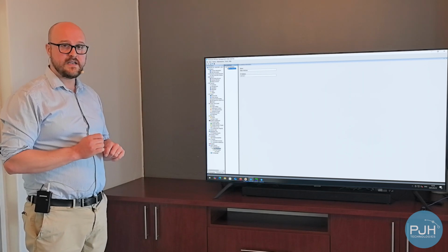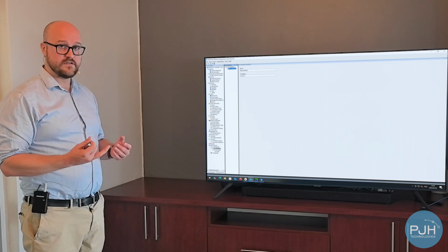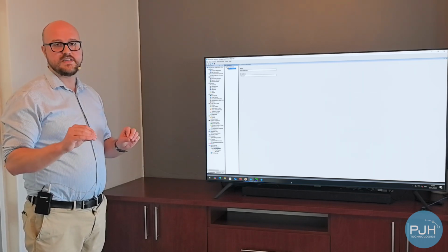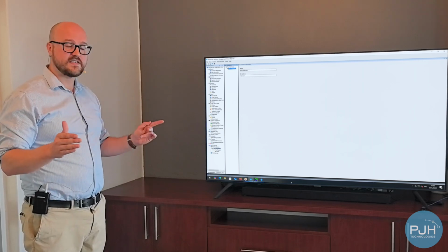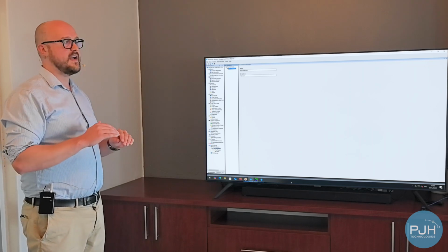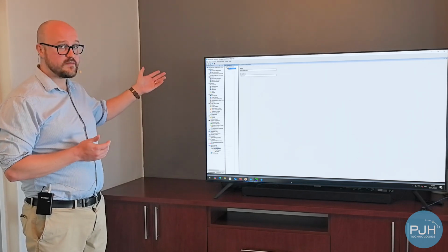With some, you can just plug a network cable directly in. Others require a Modbus conversion unit of some kind. A field server is often used for that. In all cases, a network cable is the main thing that you need to connect the fire panel and the Milestone XProtect server. And once that has been set up properly, then the rest of the configuration is all done in the software in this Milestone XProtect management client that you see here.